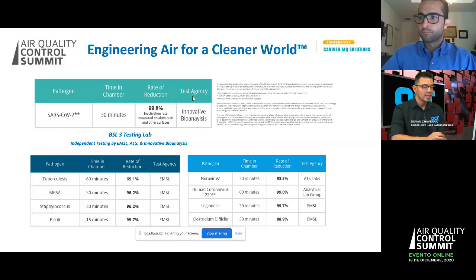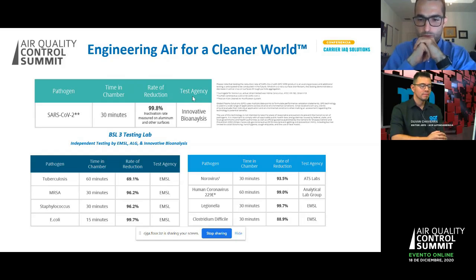Otra pregunta de Jorge Gaitán, esta está en inglés. David, I have a question, says Jorge Gaitán. Would you recommend bipolar ionization over UVC light? If so, why? I think the big advantage that needlepoint bipolar ionization has over a UVC light system that has been installed inside the air handling unit is simply that bipolar ionization can reach out into the space through the ductwork as the ionization is delivered to the space and begin actively treating the pollutants of concern there, instead of waiting for them to get back to the HVAC system like a UVC light system would require in order to be effective.